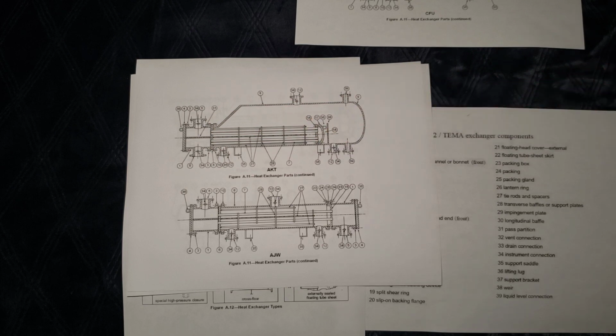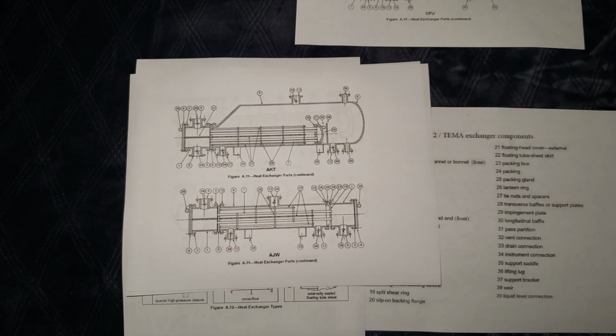A lot of people don't like it because it makes it harder to stab a bundle, and it gives you the chance of damaging the bolt studs in insertion if the bolt studs are still in place. I admit that is a scenario that can happen, but that's why you would want the tube sheet threaded. And if I describe that by listing item number 6 as threaded, that should be very obvious to everyone why that was built that way.